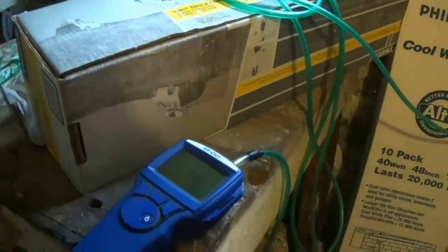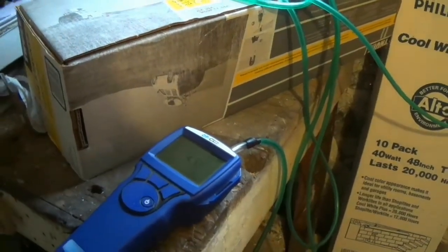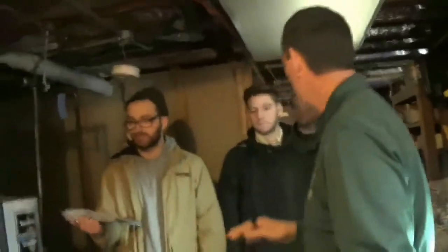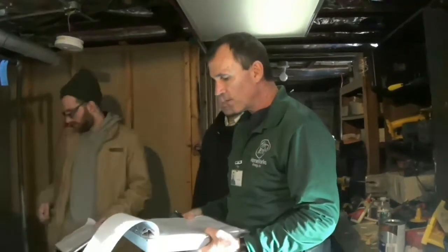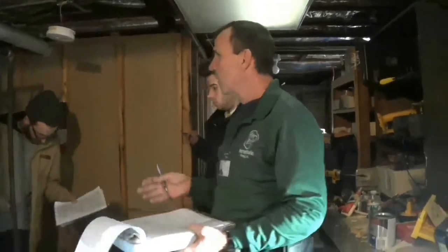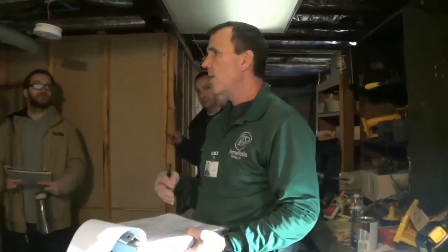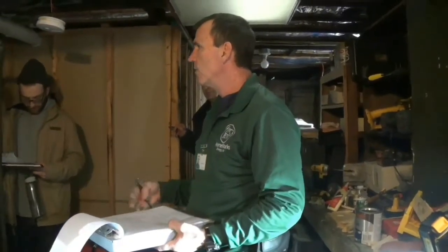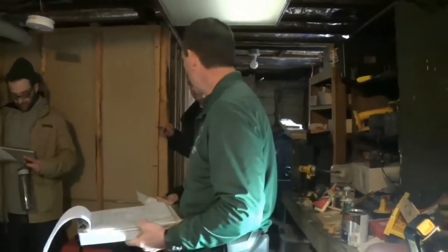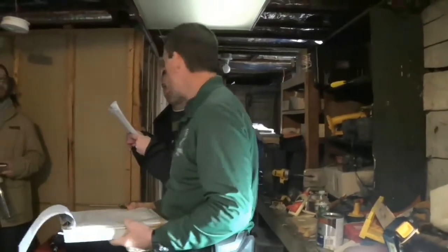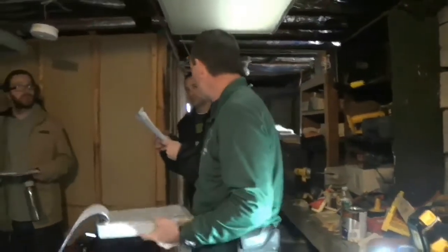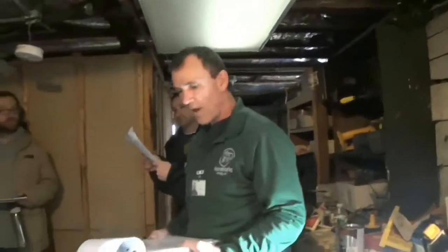Okay, so now what we're going to do is we're going to make the house fight the atmospheric venting. We're going to create what's called worst case depressurization in the house. So we've done some things with the interior doors already. We've closed all the interior doors that lead to rooms that don't have exhaust fans in them. So regular bedrooms, our bathroom in this house does not have a bathroom exhaust fan. So we've closed off those rooms that don't have exhaust fans in them.